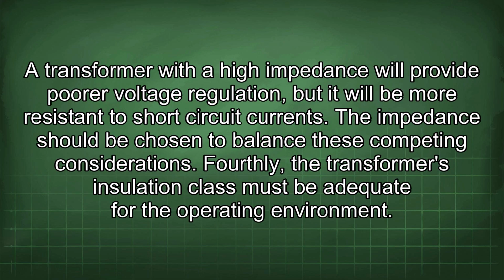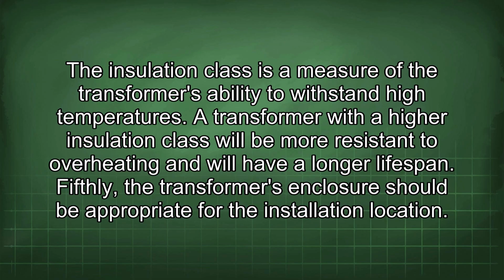A transformer with a high impedance will provide poor voltage regulation, but it will be more resistant to short-circuit currents. The impedance should be chosen to balance these competing considerations. Fourthly, the transformer's insulation class must be adequate for the operating environment. The insulation class is a measure of the transformer's ability to withstand high temperatures. A transformer with a higher insulation class will be more resistant to overheating and will have a longer lifespan.